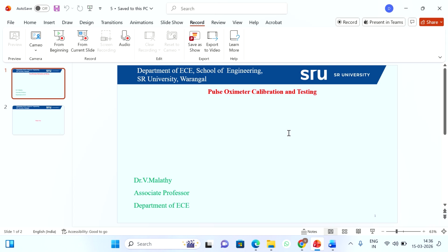Today's video lecture is on simulation of pulse oximeter calibration and testing. In this simulation, we will get a red PPG signal with noise. PPG means photoplethysmography, and then an infrared PPG signal, which is noisy.